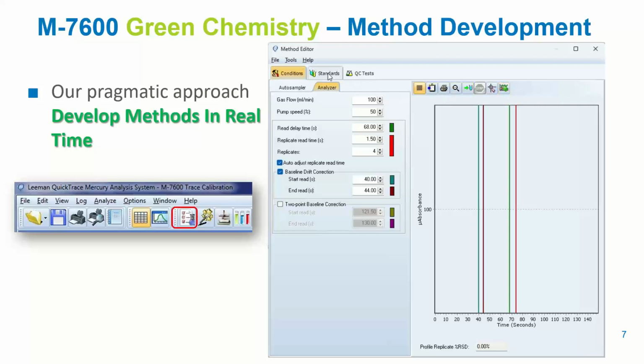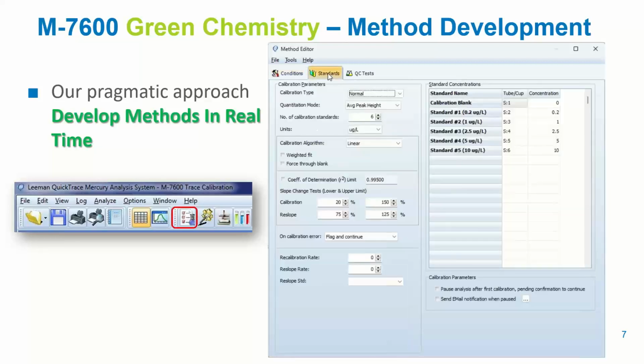All right, so let's move on to the standards tab. So we have multiple calibration parameters like calibration type. So 99% of the time, this will be normal for the M-7600. The other 2 are more for the M-8000. The quantitation mode, so we have peak height and peak area. The number of calibration standards, those will pop up in the chart to the right. You can add by clicking. You can see it adds a new one to the bottom. Our units, there's a wide variety of units already in the software. But if you feel like you need one that's not there, you can always go to Tools to define units and type in your own.